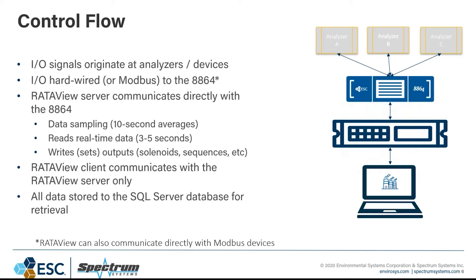The RATAView client is a Windows application — shown on a laptop but can also run on the server itself — that communicates with the RATAView server only. It doesn't communicate directly with any devices or analyzers. All the data retrieved from the 8864 is stored on the SQL server database for retrieval, so any tests you run are stored essentially forever in that database and you can go back and retrieve those at any time. RATAView can also communicate directly with Modbus devices in addition to the 8864.